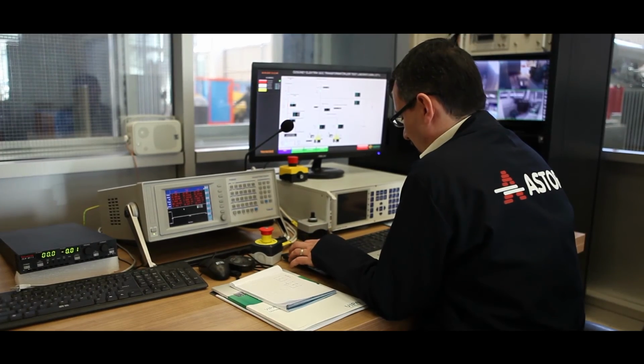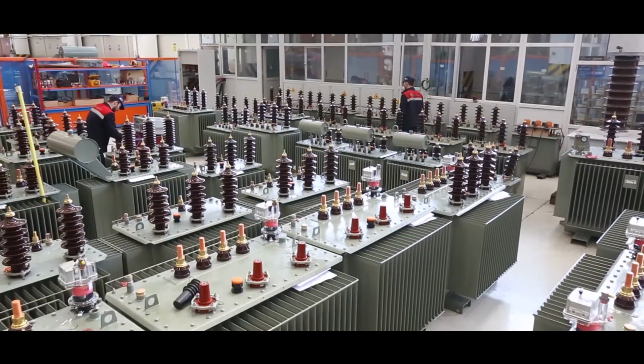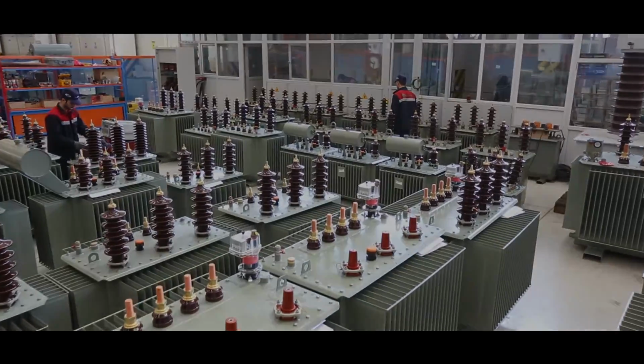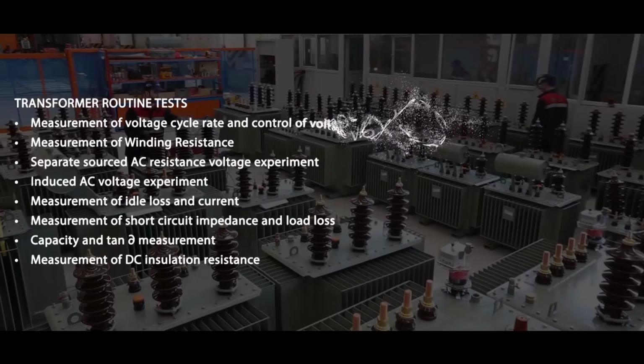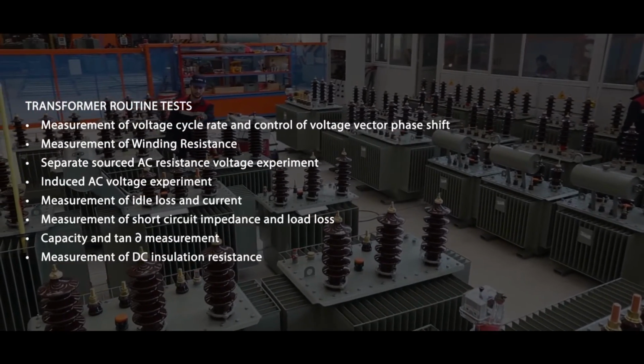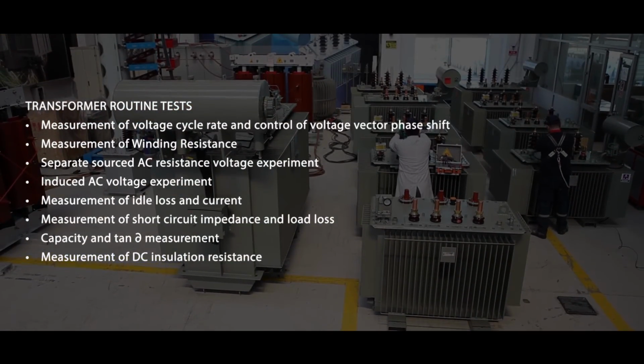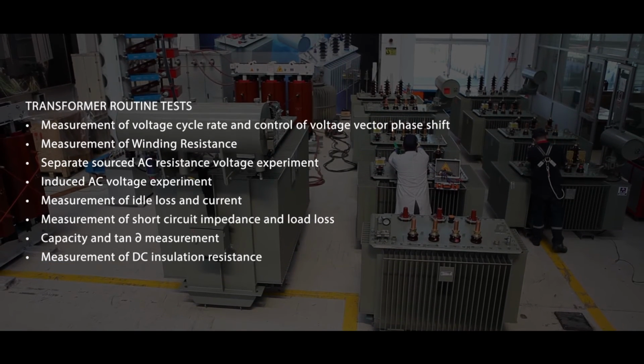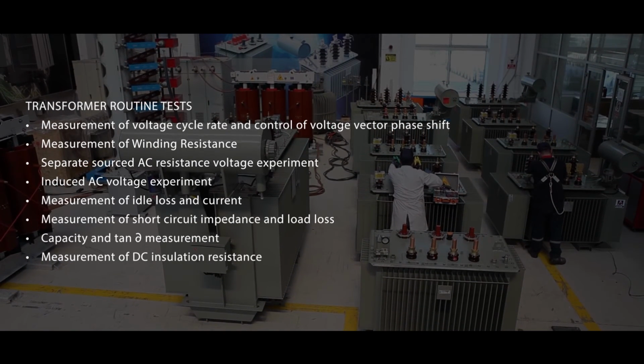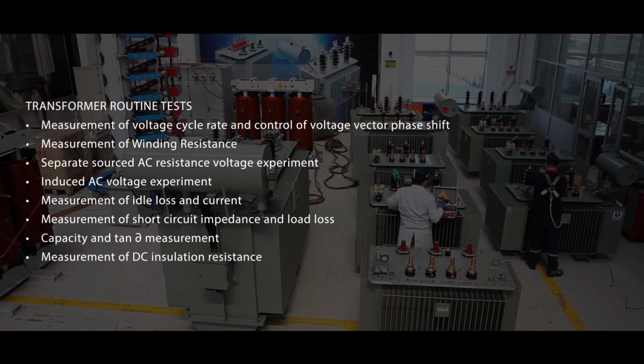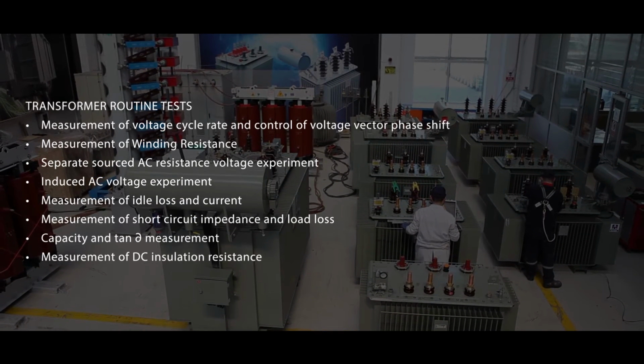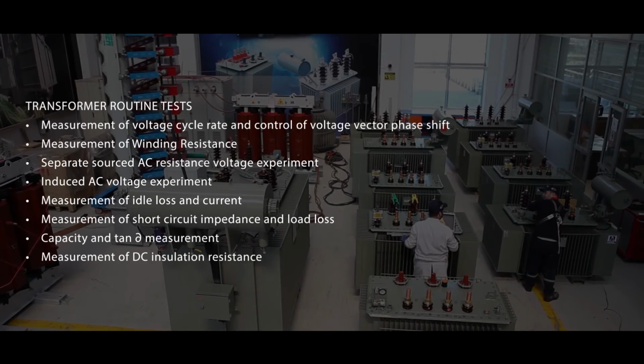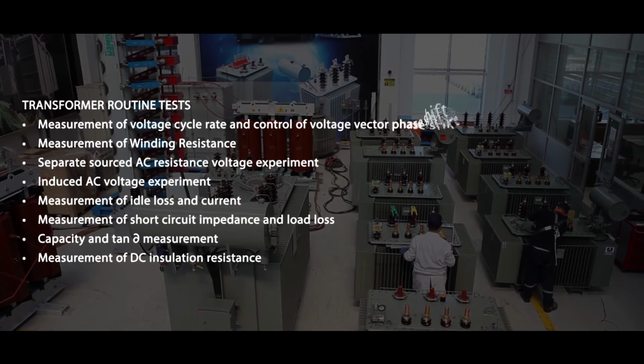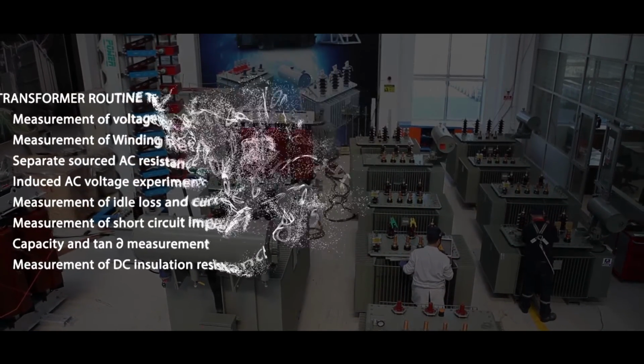Transformer routine tests. The following tests are routinely applied to every transformer manufactured at our facilities. Measurement of voltage cycle rate and control of voltage vector phase shift. Measurement of winding resistance. Separate sourced AC resistance voltage experiment. Induced AC voltage experiment. Measurement of idle loss and current. Measurement of short circuit impedance and load loss. Capacity and tan delta measurement. Measurement of DC insulation resistance.